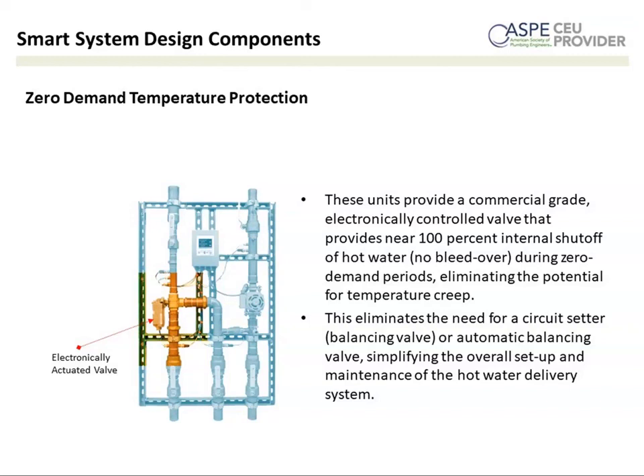That historically resulted from traditional mixing valves where the shutoffs weren't really tight and there was leakage. The hot water would leak to the cold and warm the cold water up during a zero demand period, and this would be in a closed loop. Over time, theoretically, your hot water could get to the temperature of your boiler. In this type of system with 100% hot water shutoff, it eliminates that risk. You can follow up if you want more information around this, and we can go into more detail after. But it's a huge benefit.